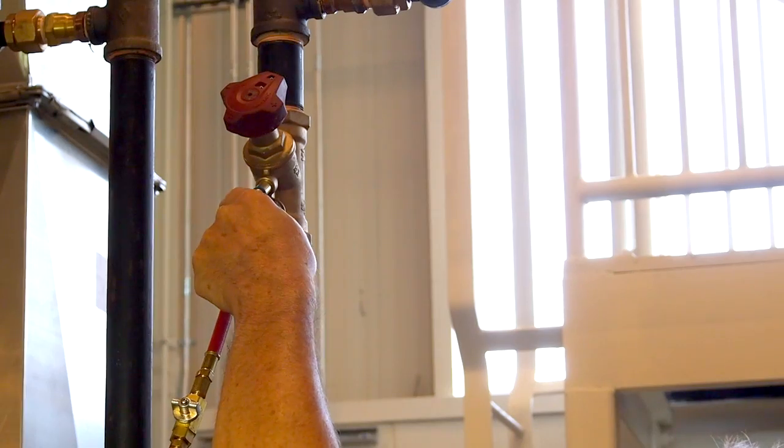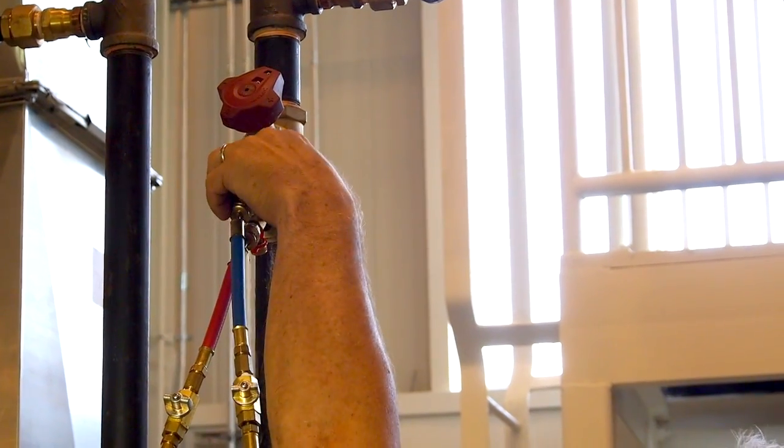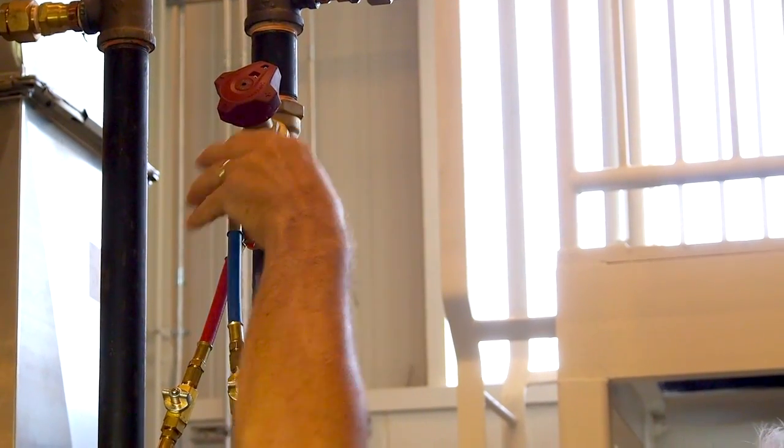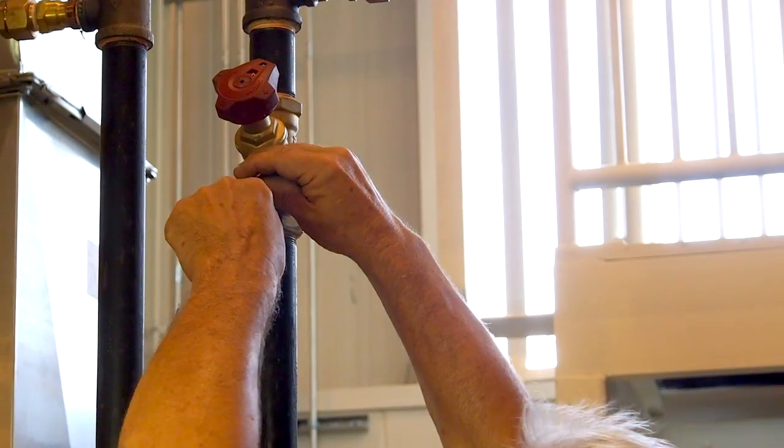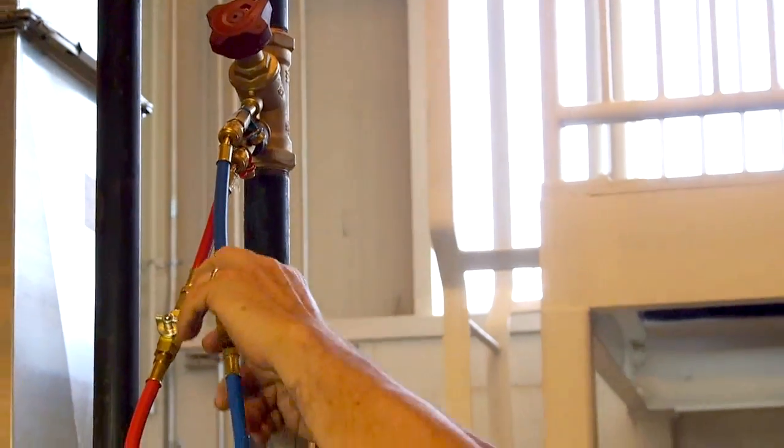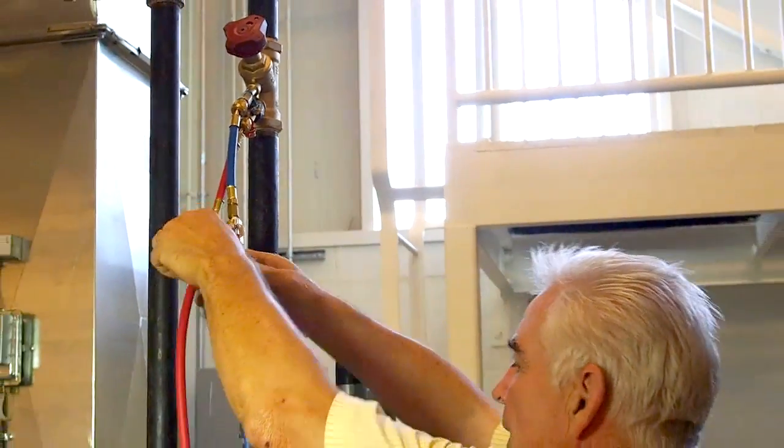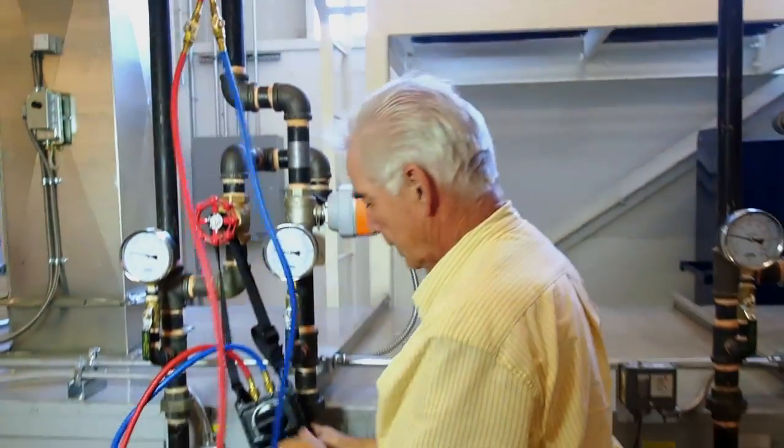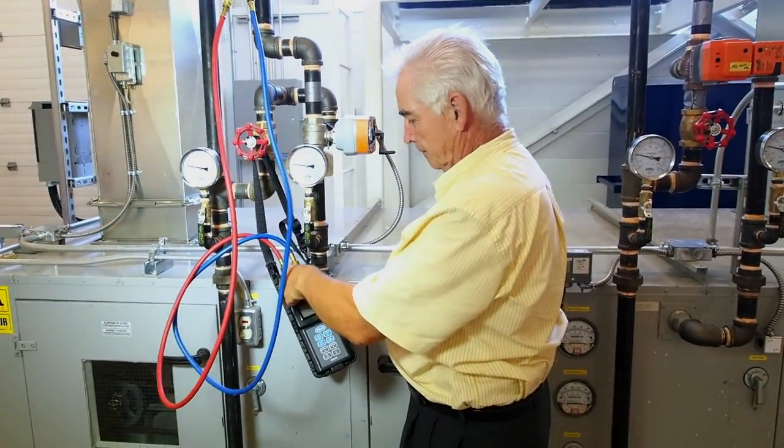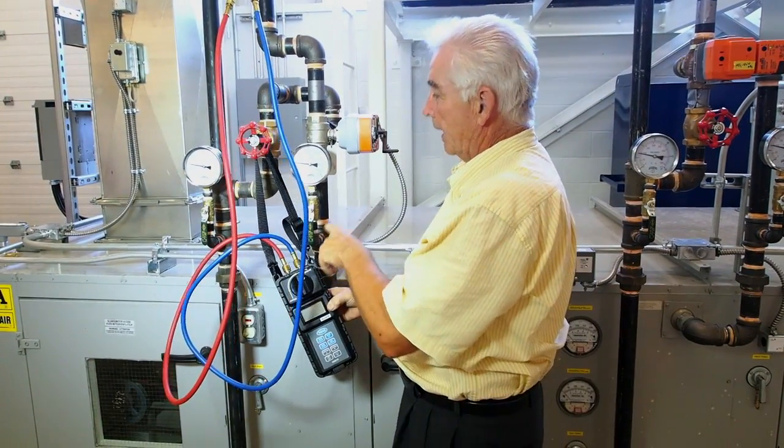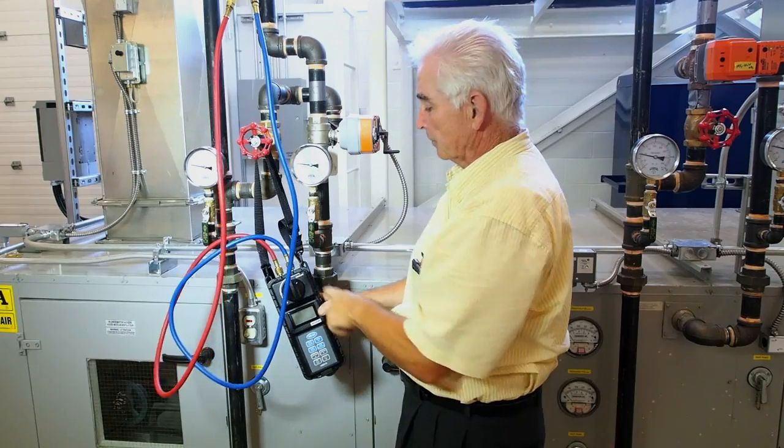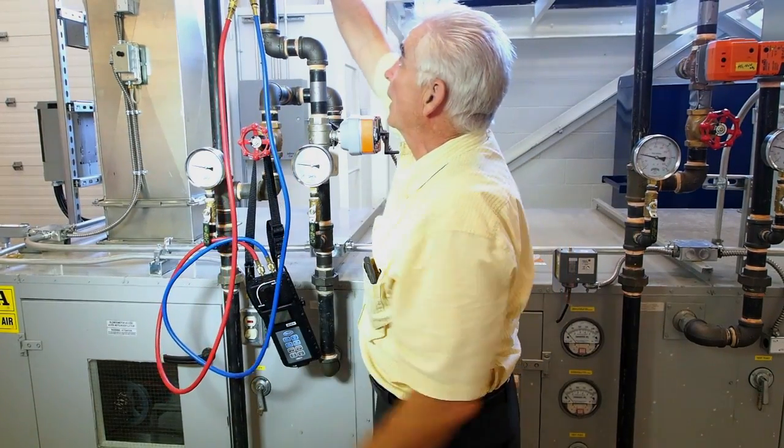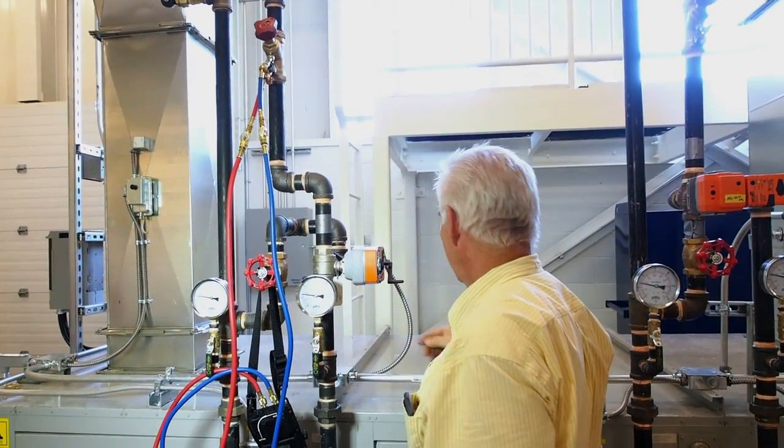They always drip a little bit. So you open these, you've got it set on bypass, and then you turn it to measure and it records the differential pressure across this circuit balancing valve.